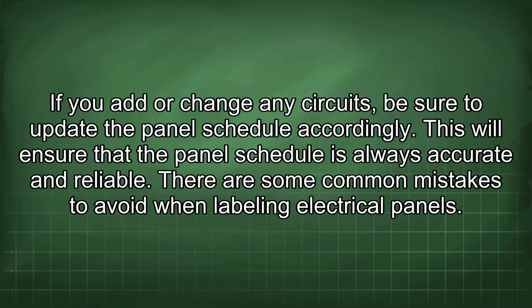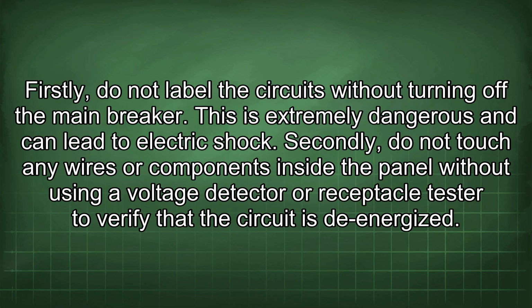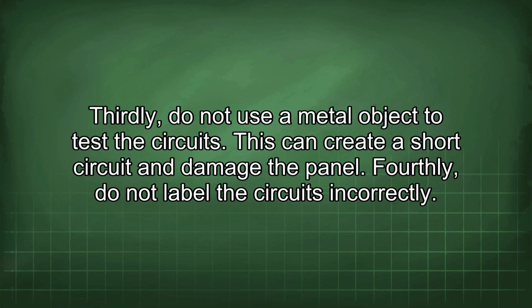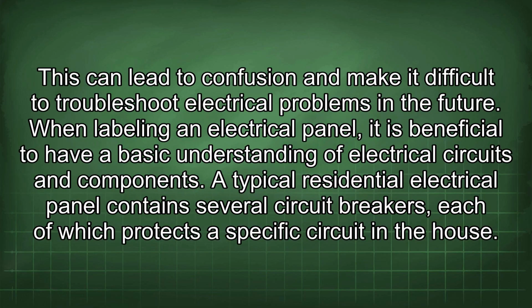There are some common mistakes to avoid when labeling electrical panels. Firstly, do not label the circuits without turning off the main breaker. This is extremely dangerous and can lead to electric shock. Secondly, do not touch any wires or components inside the panel without using a voltage detector or receptacle tester to verify that the circuit is de-energized. Thirdly, do not use a metal object to test the circuits. This can create a short circuit and damage the panel. Fourthly, do not label the circuits incorrectly. This can lead to confusion and make it difficult to troubleshoot electrical problems in the future.